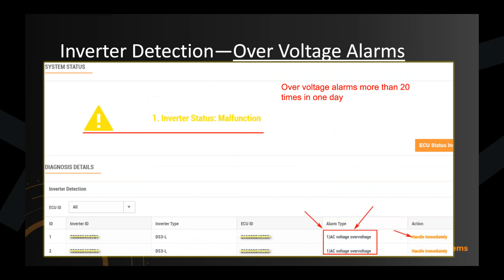We also sometimes see overvoltage on the AC side. For example, the voltage is 266, which is a bit high for our 240 grid. In this scenario there are two solutions. The first is to call our tech support to expand what we call the AC parameters of the microinverter. With any inverter technology, it's only going to push power if the 240 voltage on the AC side is stable, and if it goes over certain limits, it will shut itself off, thinking the grid is unstable and it needs to stop pushing power.